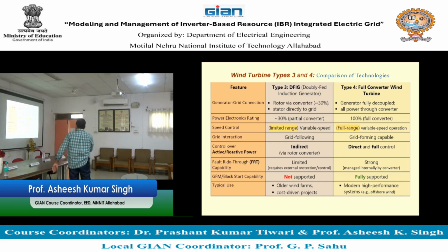Second point is speed control. When control is applicable only on the rotor part, as in type 3, only a limited range of variable speed is available, because you have control over almost 25 to 30% of power. But in type 4, you have full range control.